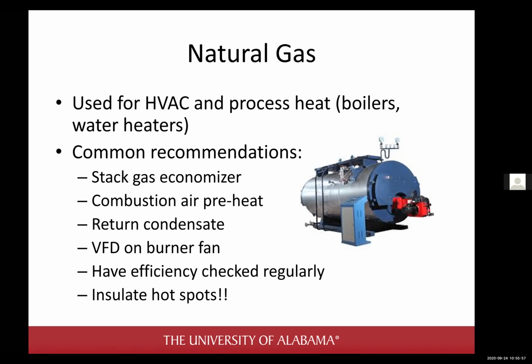They'll actually do a tune-up. There are little linkages, and they'll tune it so you're using less excess air than you need to burn. I don't want to get too into the weeds, but you don't want to use too much excess air, a marker of which is the percent oxygen in the stack gas. If you use too much air, the flame won't be as hot, and you won't boil water as effectively, because too much air is going along for the ride.